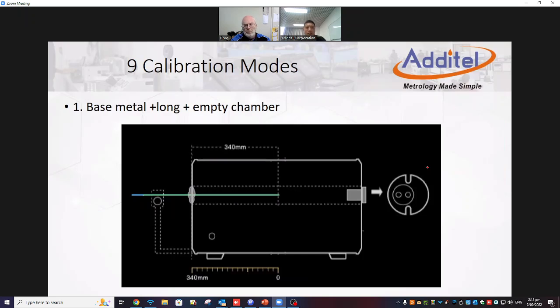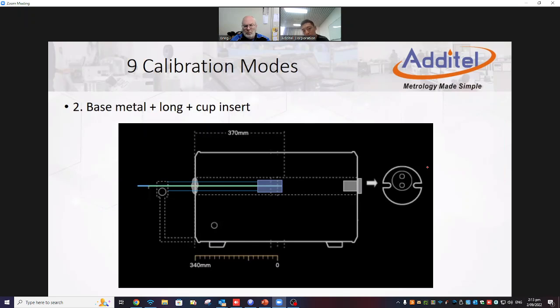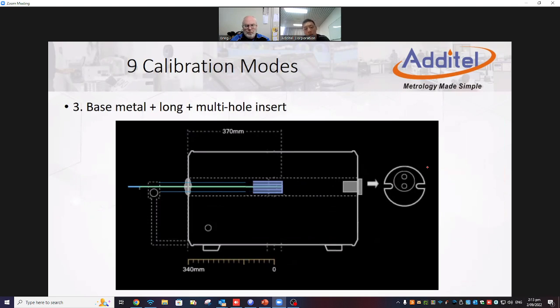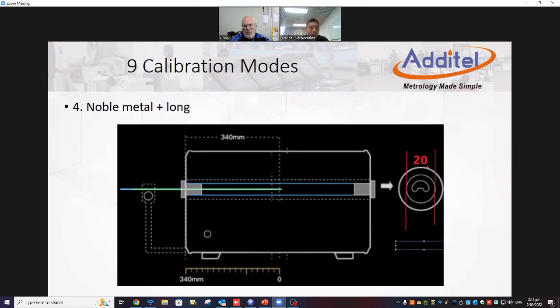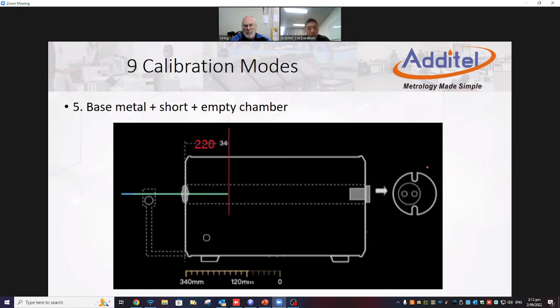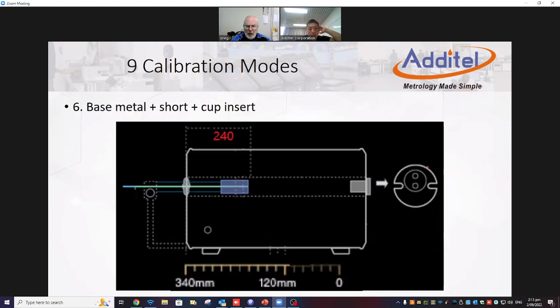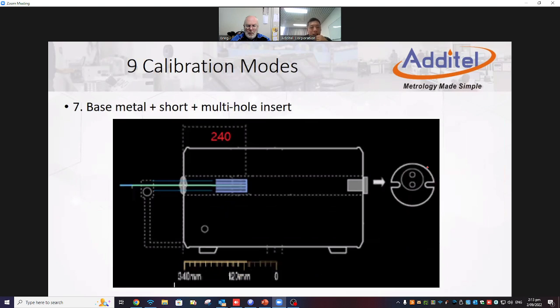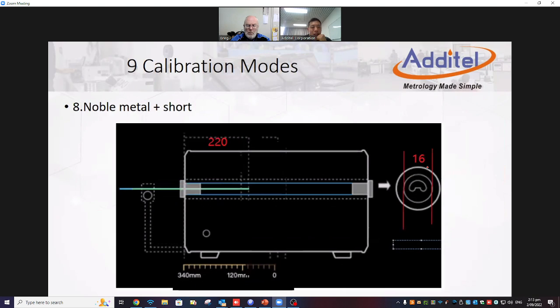We do have 9 calibration modes inside the program: base metal long and empty chamber, base metal long and cup insert, multiple insert, noble metal with long, base metal short empty chamber, short with cup insert, short with multi-hole insert, noble metal with short, something like that.